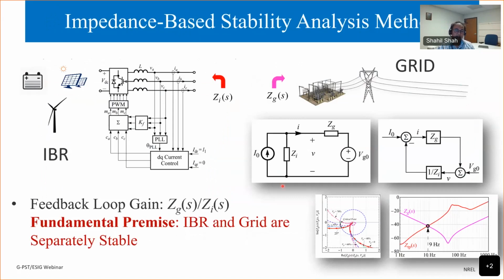So what you see on your screen is basically the standard approach of impedance-based stability analysis. If we have an inverter-based resource with the output impedance of Zi, which really represents the impedance not just at fundamental frequency, but for a broad frequency range, and if that is connected to a grid with internal impedance Zg, then we can represent the IBR by a Norton equivalent circuit, or basically a steady state current source in parallel with the inverter impedance, and the grid by a Thevenin equivalent circuit, or a voltage source in series with the grid impedance.